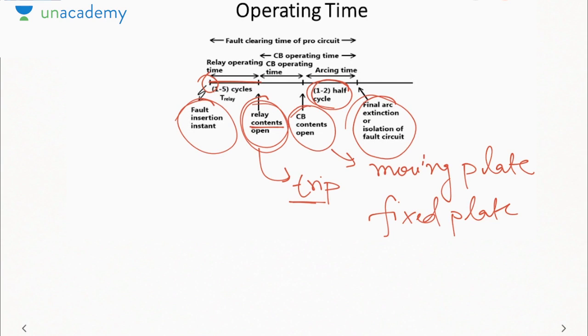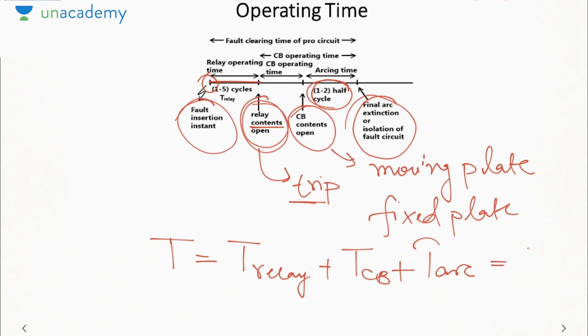Do not think that anyway the arc will extinguish in 1 or 2 half cycles. We have to remove the arc, otherwise it will keep on existing. So the total time of fault clearing becomes T relay plus T circuit breaker plus T arc. That is your clearing time. This clearing time must always be less than the critical clearing time for system stability that we studied.